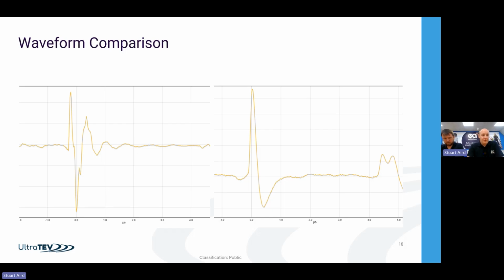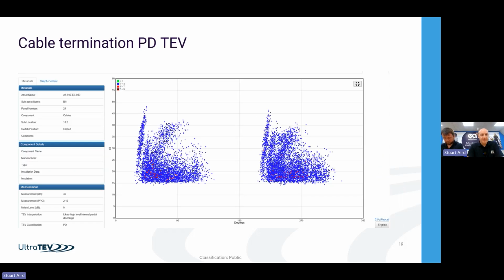So then we decided we'd also take a transient earth voltage measurement, same as we did with the previous one. Again, we've got a really clear partial discharge pattern on the transient earth voltage sensor for this one. Because it's local, with a lot of high frequency, we can see a clear TEV signal. So this clearly differentiates it from the previous measurement and indicates that there's a problem in the cable termination local to the switchgear. The level on this as well is in the red threshold. So in this case, we recommended that the customer does take an outage and tries to narrow down further, but it's in the cable termination of a particular phase. So much higher frequency, much more distinctive pattern than the previous one.